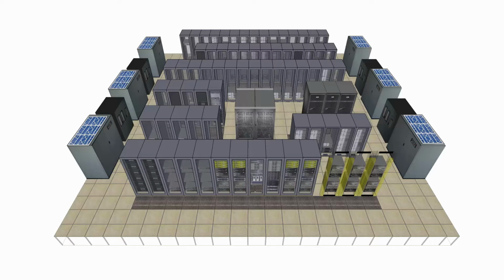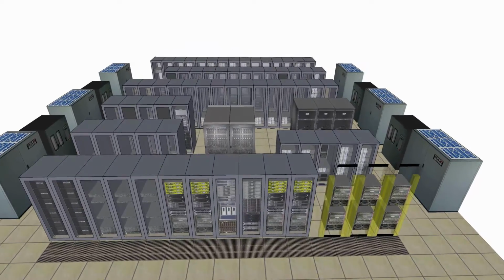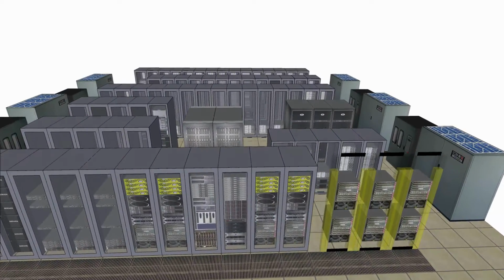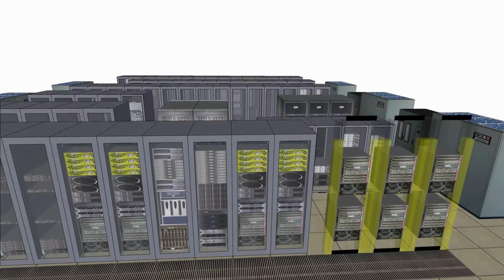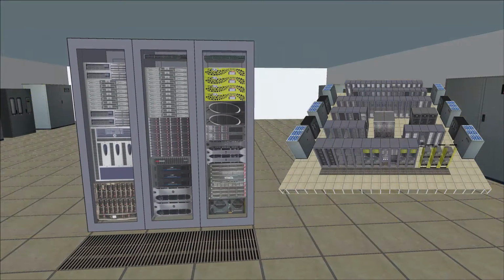We're going to examine an N+1 data center with 6 cooling units. We can test ACU failure scenarios for each of the 6 units and assess the resiliency of our cooling infrastructure. To highlight the unpredictable effects associated with ACU failure, we're going to track a group of 3 cabinets and see how the installed IT devices are impacted by each failure scenario.